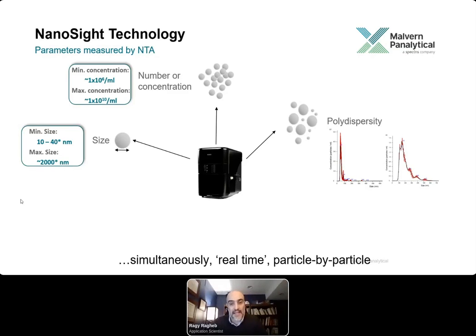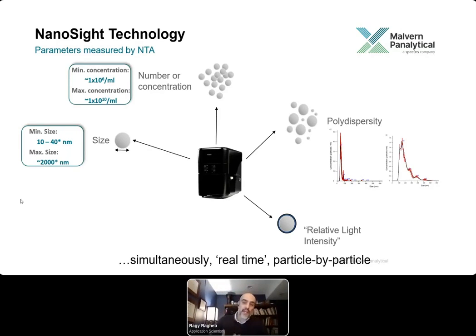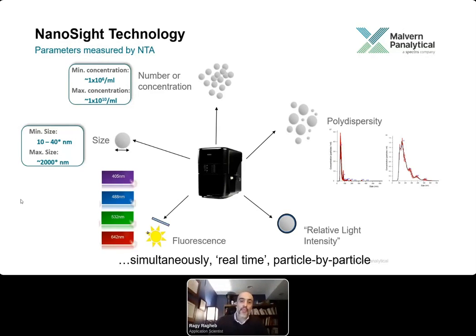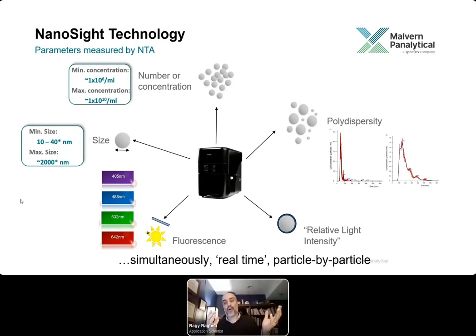Because it's a particle-by-particle analysis, you can gate on certain sub-ranges and get percentages and concentrations of a sub-range compared to the total population. You can also look at relative light intensity — for example, if nanobubbles are present alongside metals and metal oxides of the same size, you can gate around each population separately. NanoSight also offers the ability to measure fluorescence with a choice of four different laser modules and corresponding long-pass filters, letting you compare fluorescently labeled particles to the total population.